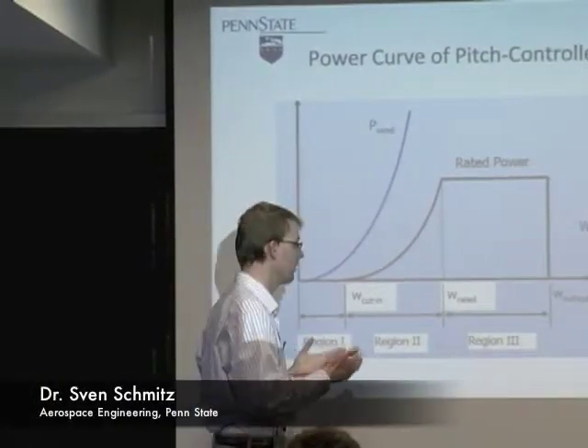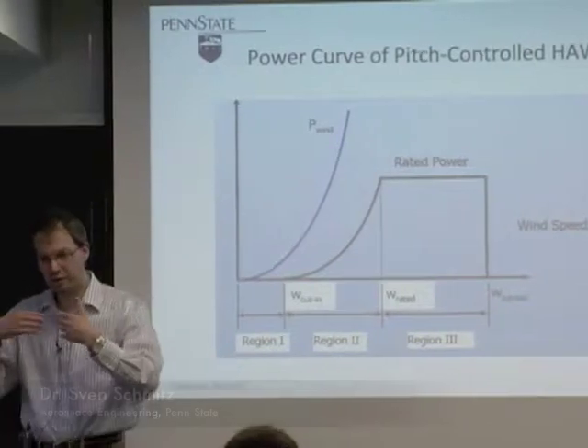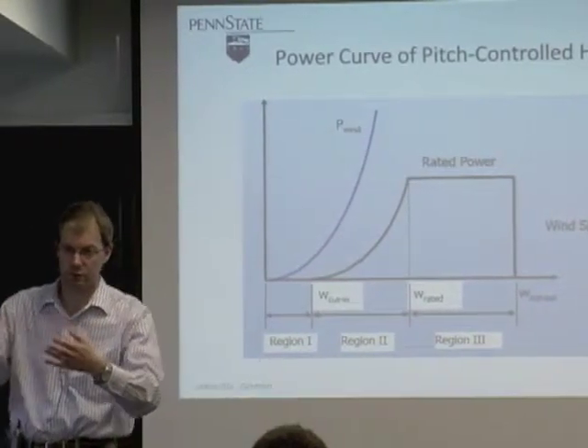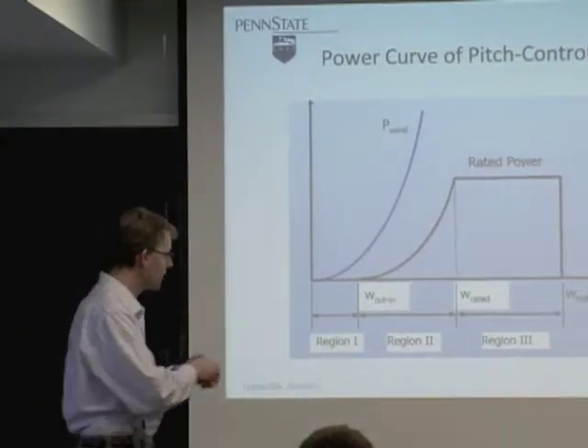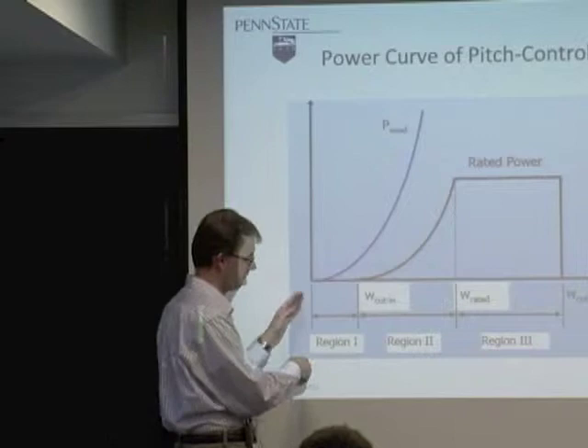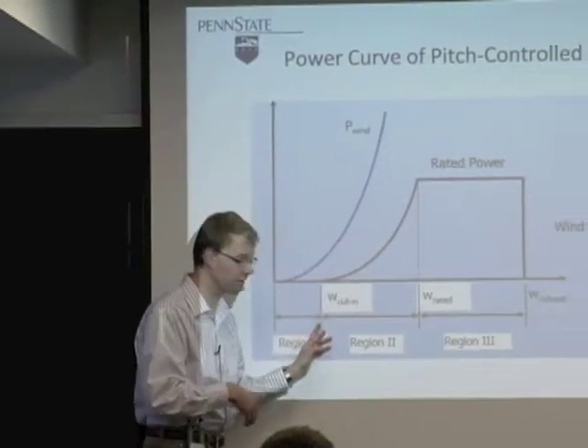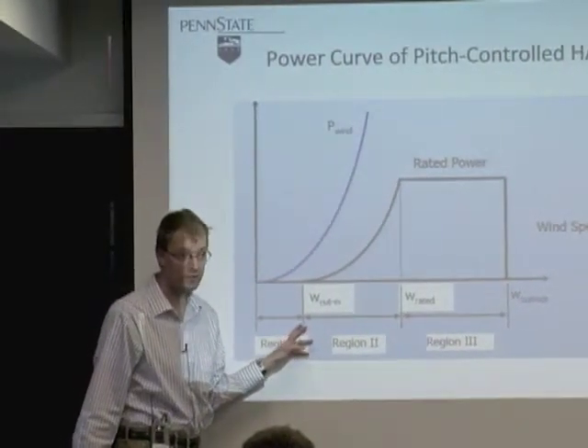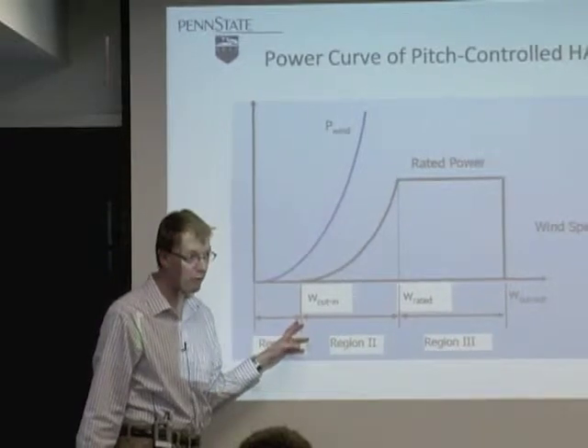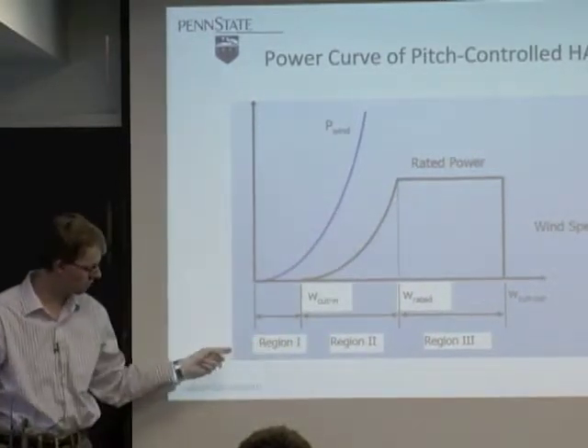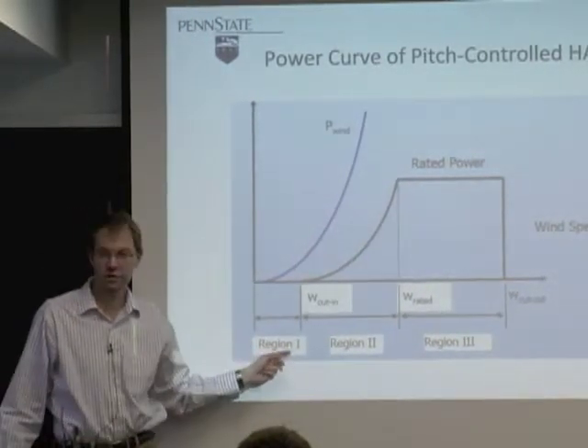A real wind turbine, if you look at it, is going to take a bit of wind speed to start it. There is a region from zero wind up to a certain wind speed called the cut-in wind speed where there's no power produced by the wind turbine — also called Region 1.